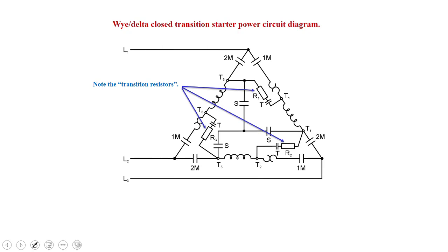We also have a closed transition starter when we're talking about Y delta. What they make use of here is something called transition resistors. It's kind of the same sequence, so we're going to run through it. At the beginning, when I press the start button, the same thing happens. 1M closes and the star contacts close. So right now, if we follow it, they are connected up in Y. The next thing to happen is when the timer times out. The transition resistors, T for transition, would close, so we have a parallel path there.